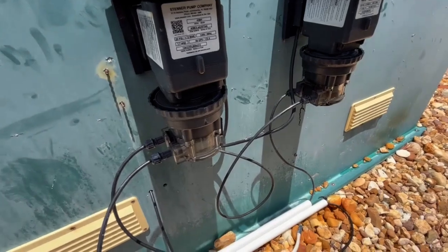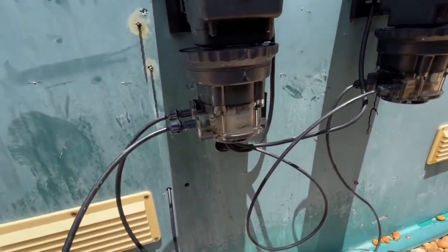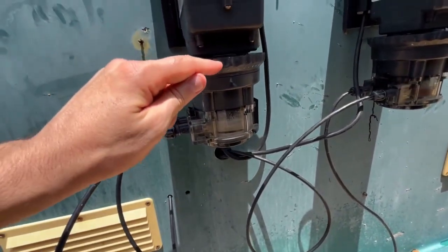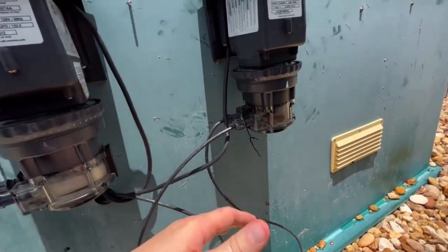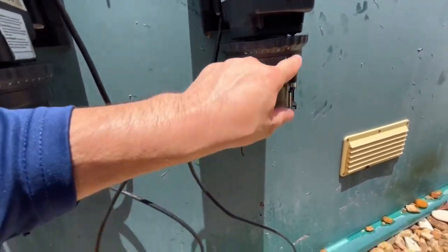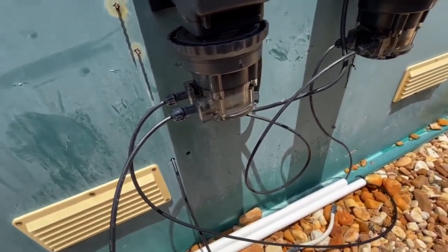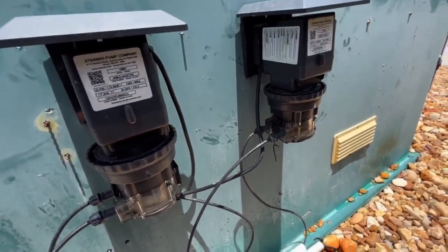Here are the lines. We have a whole course on this. These lines get clogged. They don't work, the feeders trip. And again, down here you can see the settings. Sometimes the settings aren't right, like the speed it pushes the chlorine. You can over-chlorinate the pool. You can put too much acid in the pool depending on the rate it's running at. These break all the time. Air gets in them, it gets crusty. You have to check them. We have a whole course on that we're going to go over.